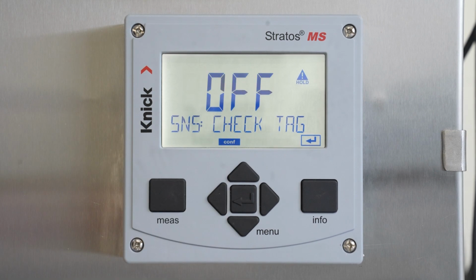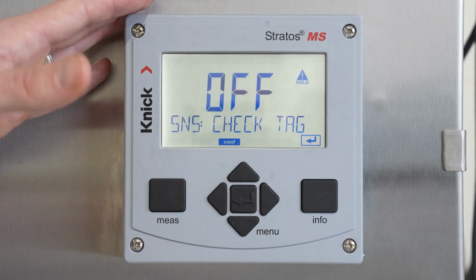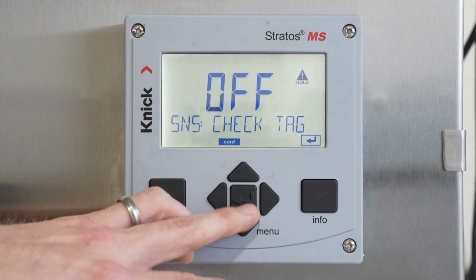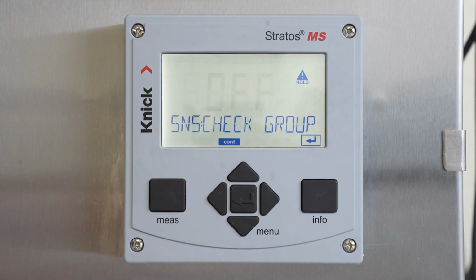It also allows for checking of the Memosens tag. This feature is beneficial for ensuring that properly tagged sensors are used with specific transmitters. We can also allow group checking with the Memosens technology. The group checking allows us to group our Memosens sensors and define which group can be used with our Stratos MS transmitter.